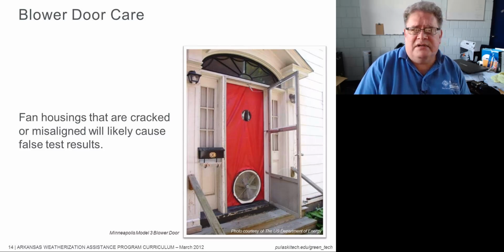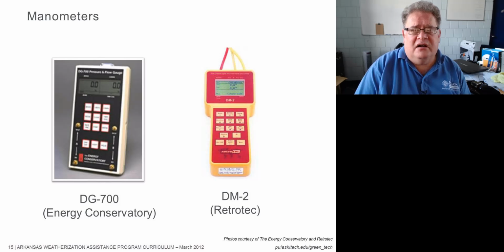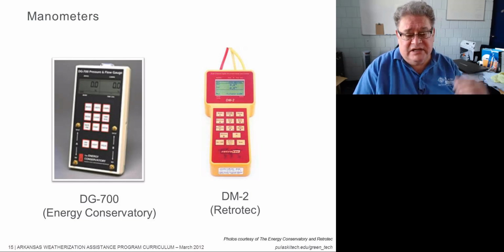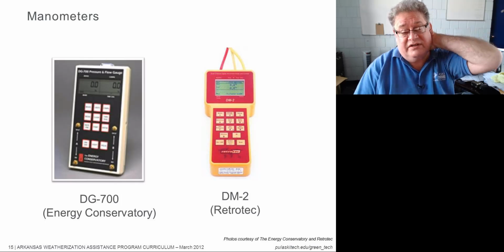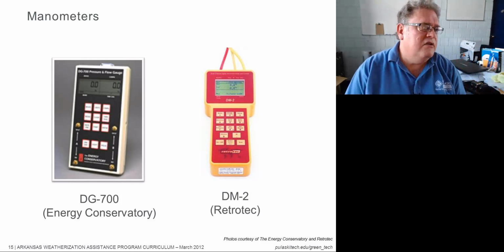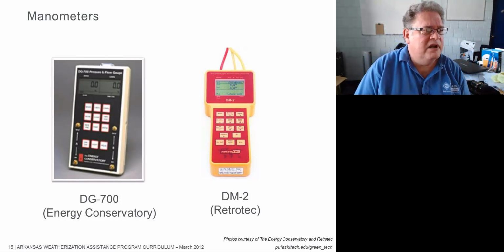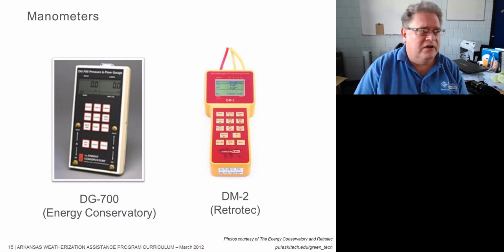All right, manometers. There are several more manometers available than just these two, but these are probably the two most popular, the DG700 from the Energy Conservatory and then the DM2 from Retrotec. They're both very good manometers. We use them to measure leakage rate on the shell. We use them to measure draft. We use them to measure duct leakage and fan flow rates and zonal pressure differences and all kinds of things. This is the backbone of what we do as far as diagnostics go.